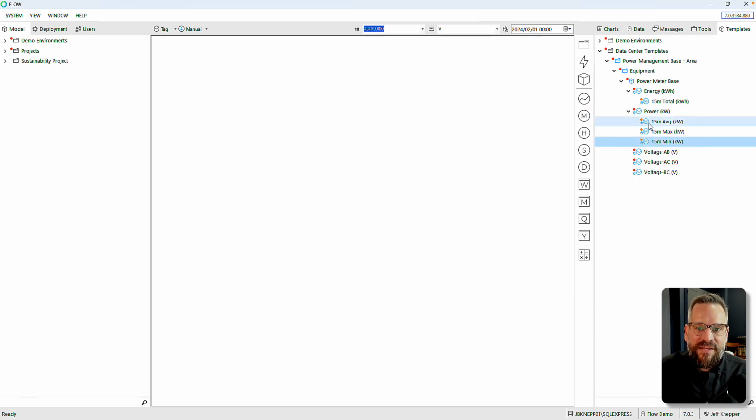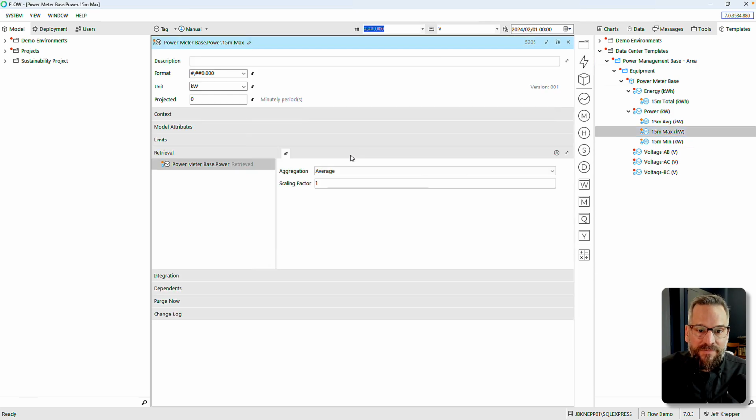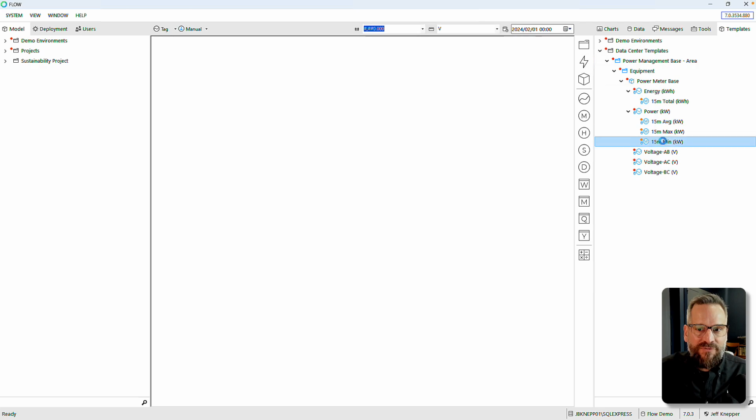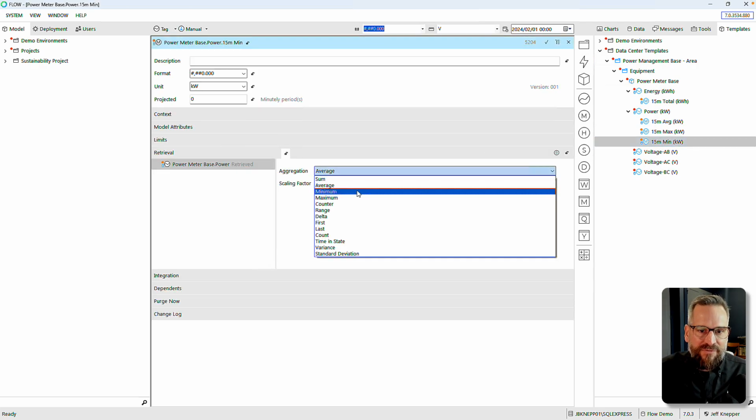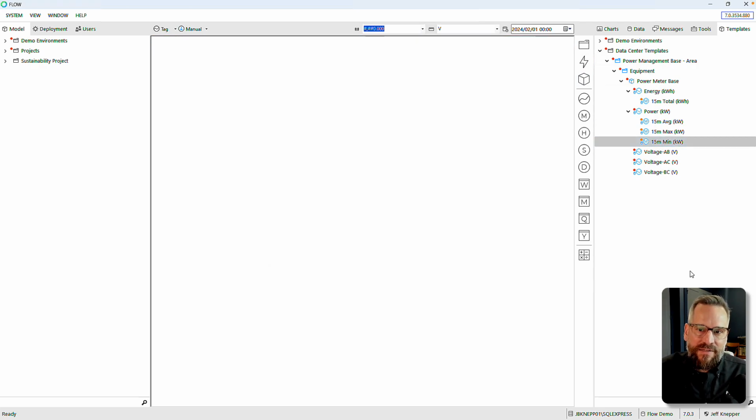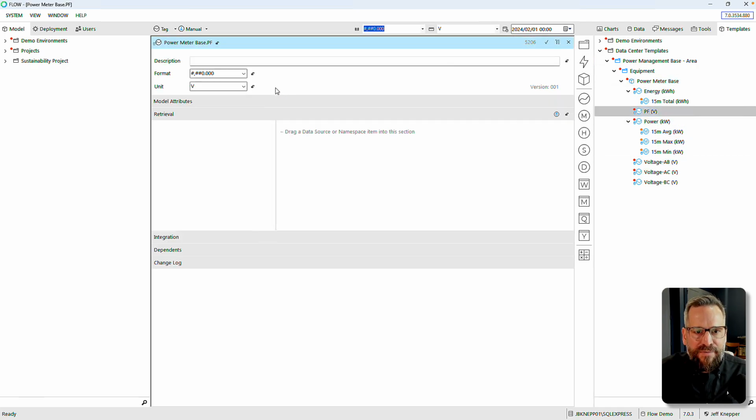Now, the reason I'm getting 15 minutes instead of 1 minute is that on my calendar in the toolbox, I've gone ahead and said I want 15 minutes to be my minimum amount of time when I create a minutely measure. I could have this as small as 1 minute. In that case, I would take the 1 minute and create a 15-minute or a 10-minute or a 5-minute from it. All right, creating some more tags.